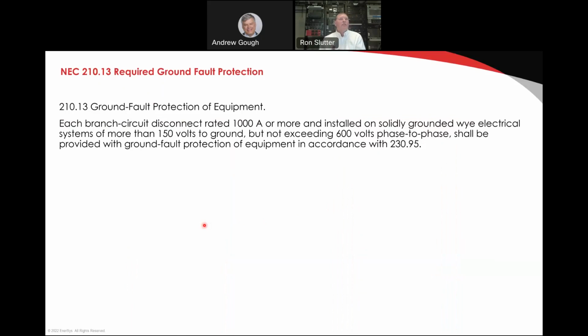All right, moving on, let's talk about some of the industry requirements that are now coming into play because of capacity improvements in the infrastructure. If you've been around, you know that the electrical services in your facilities have been upgraded and upgraded and upgraded, sometimes 2, 3, 4 times. So we are now getting into a situation where people are requiring 480Y/277 volt 3-phase 4-wire to feed the amount of capacity that's required in the facility.